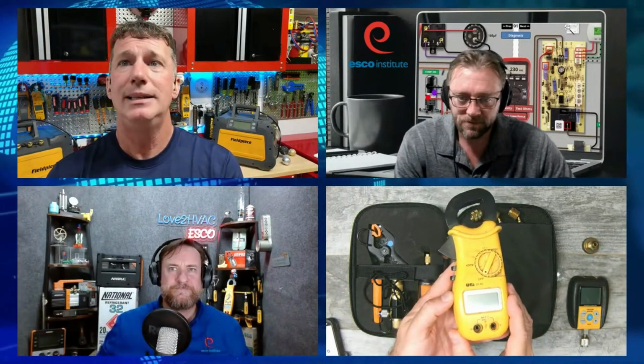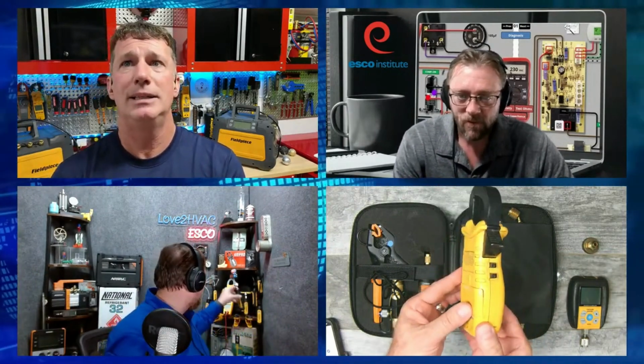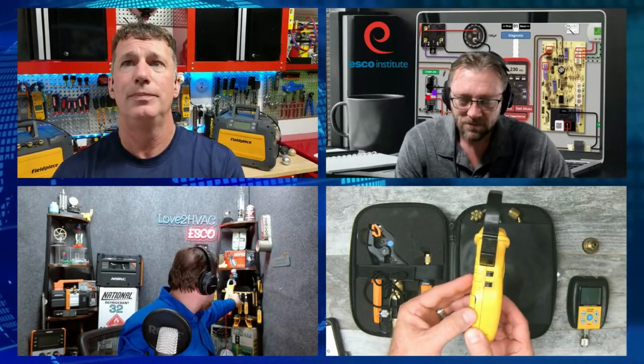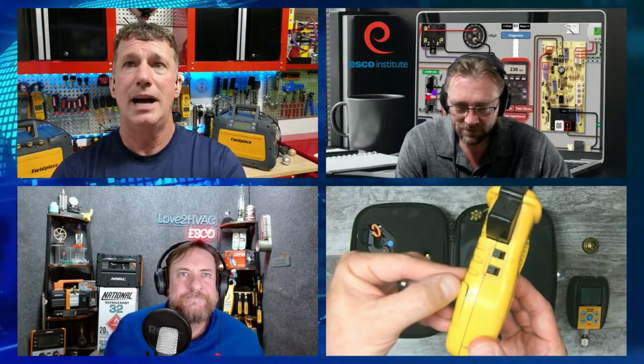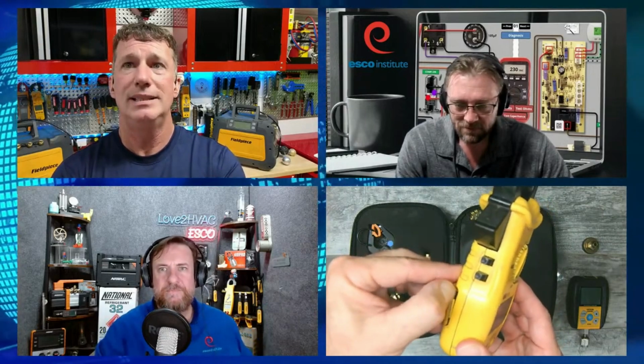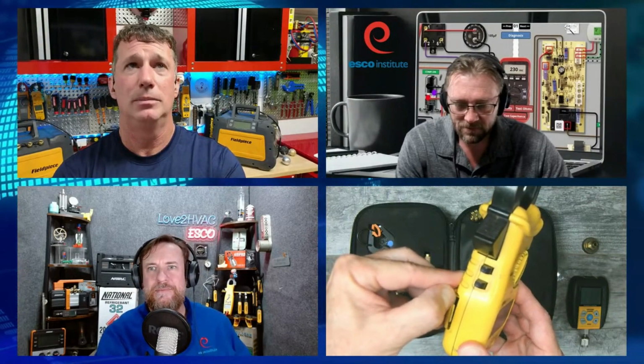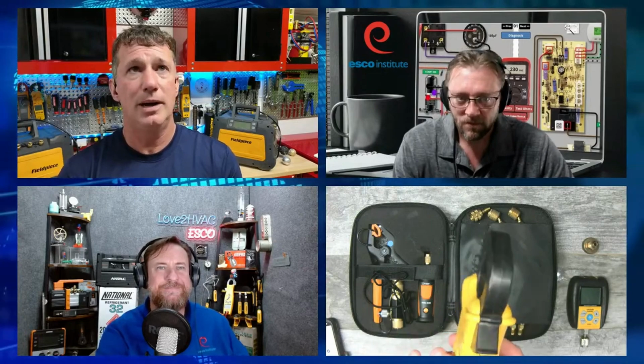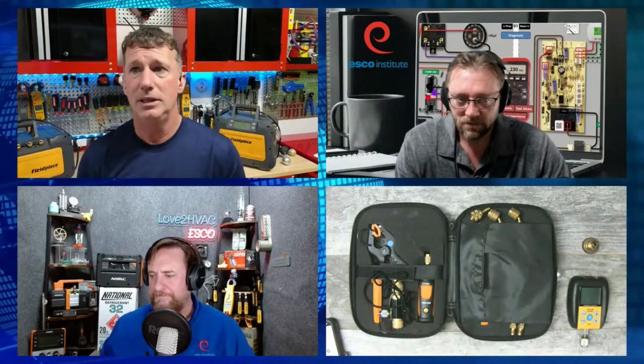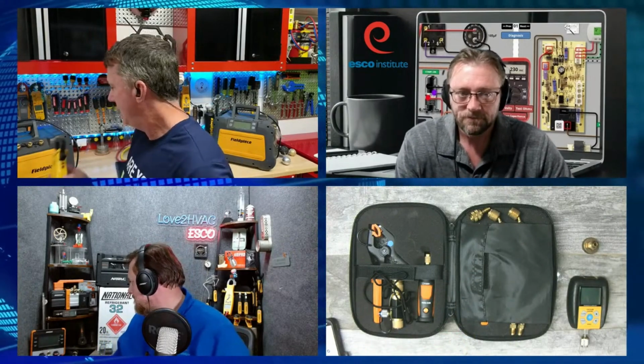Now, what about my DL40 from about 1991 or '92? Well, you can notice immediately on my battery compartment, this meter was not designed with a sealed battery compartment, right? There's no way a tool manufacturer could look at a tool that has an exposed battery compartment and allow that to be utilized for A2L refrigerants.